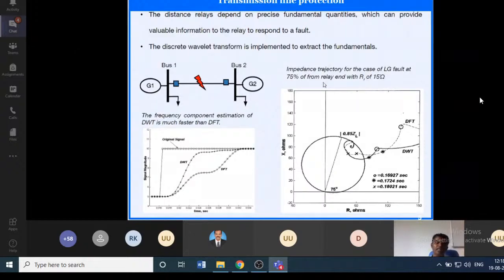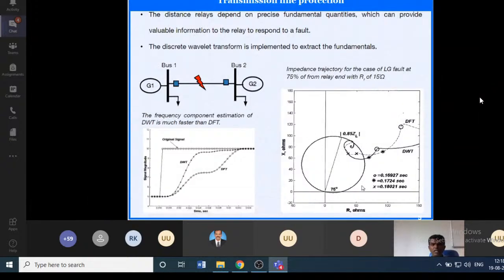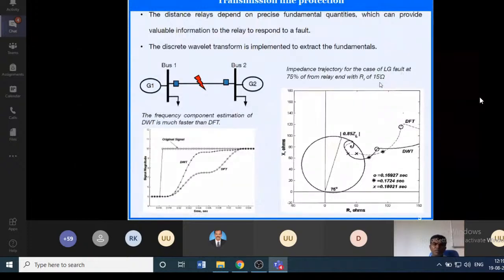So let us see the measurement in the impedance relay. Here the figure shows the RX plane of the Mho relay characteristics, which is used for transmission line protection. Here the LG fault is considered with the fault resistance of 15 ohm, right? Here the impedance trajectory is given in the RX plane.